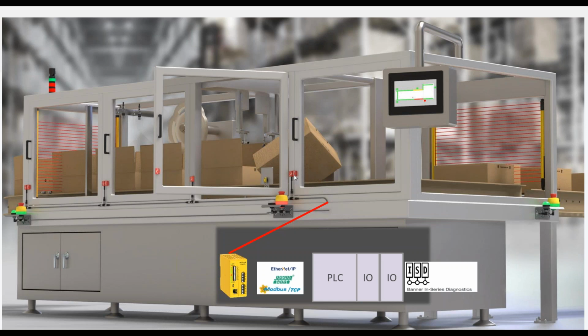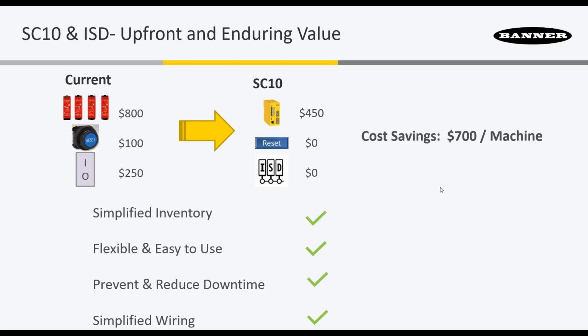So for all the door switches, in this case it was 6 door switches, they're connected to T connectors and a 4-pin cable, 2 wires go back to the SC10. The E-Stops, starting in August, we're going to have our Illuminated E-Stops that also have this in-series diagnostic feature, and you can connect them, again, 4-pin cables, T connector, back over 2 wires into the SC10. And that simplifies the overall system. And what that can do, not only saving on costs and relays and everything else, but this reduces an IO card. So it has an incremental savings there versus doing this with the auxiliary wires. But also the wiring is a big deal.